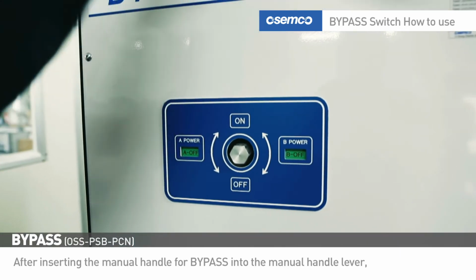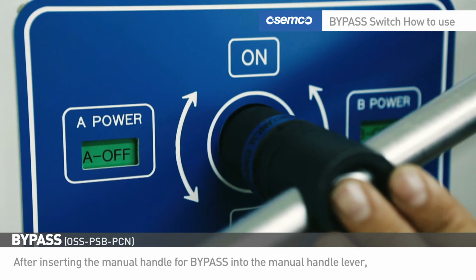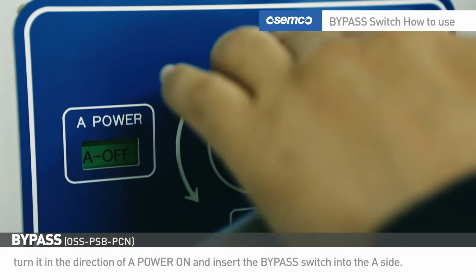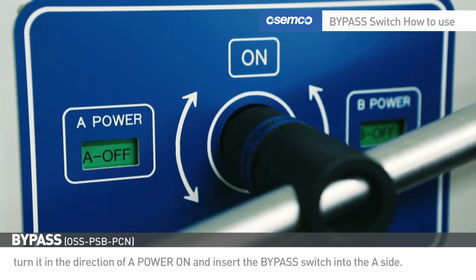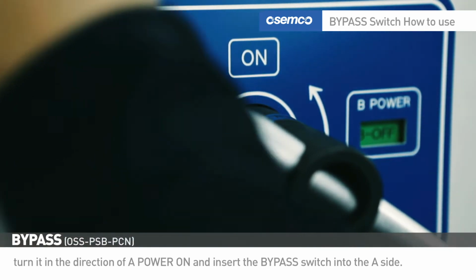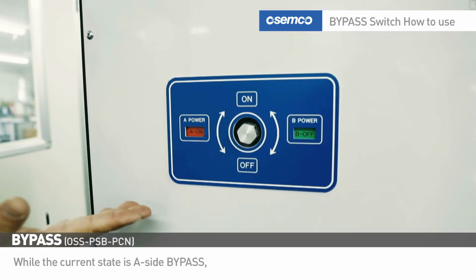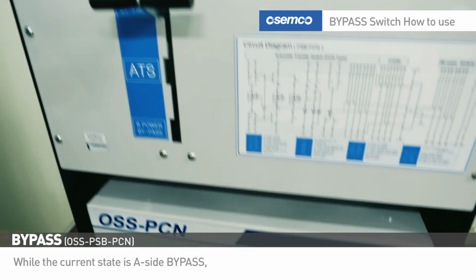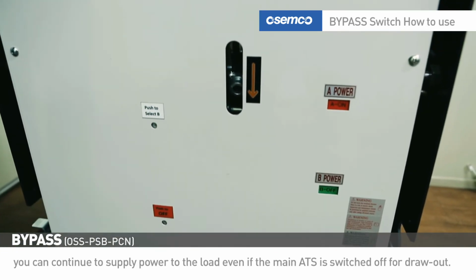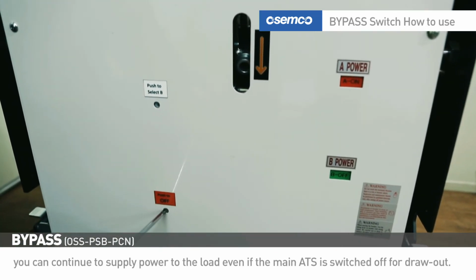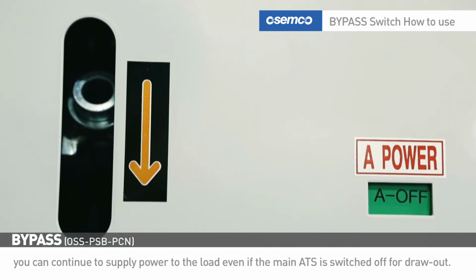After inserting the manual handle for bypass into the manual handle lever, turn it in the direction of A power on and insert the bypass switch into the A side. While the current state is A side bypass, you can continue to supply power to the load even if the main ATS is switched off for drawout.